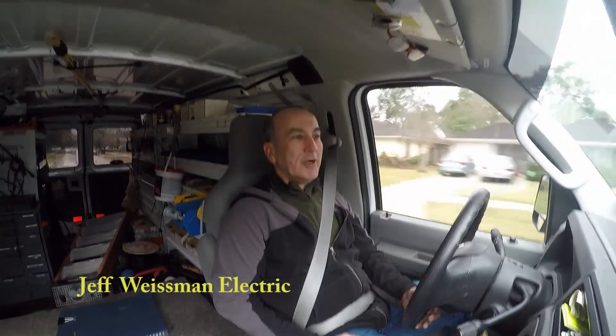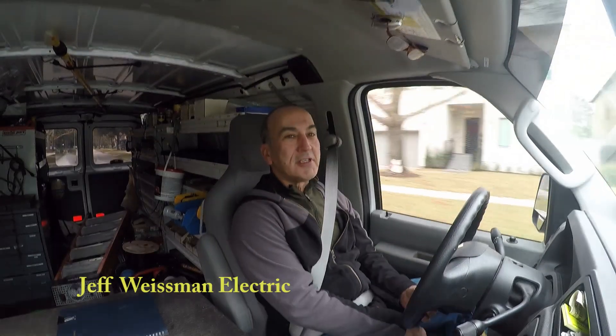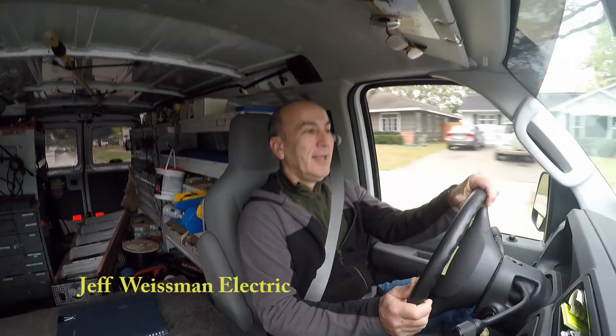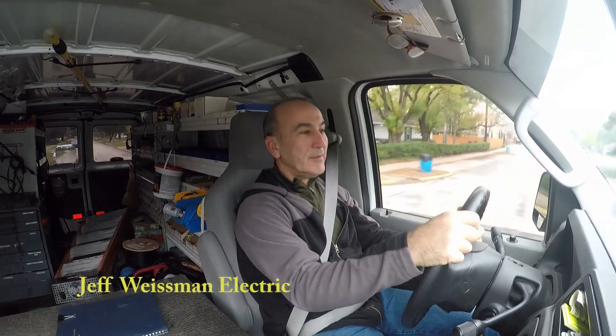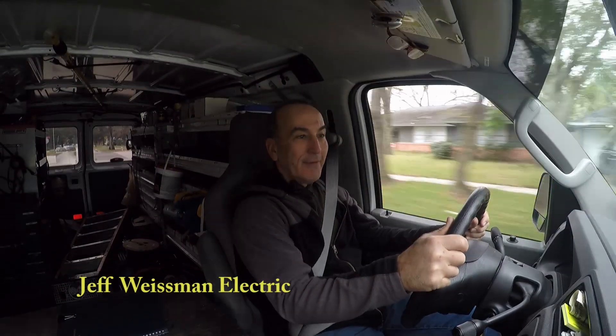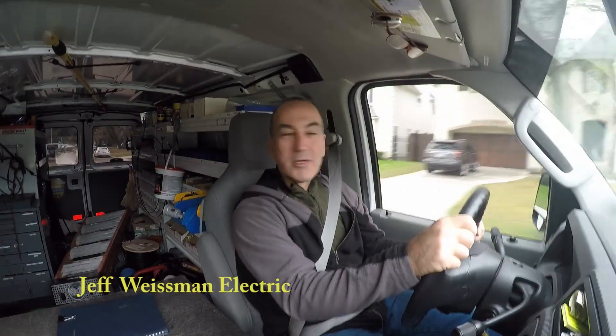So that's a way to get rid of the nuisance. The other way to get rid of the problem is to wait for those Christmas lights to dry out, or find where the nail or staple is in the wires — but that's not very practical. And if it rains again or your sprinkler system kicks on, it's going to happen again. I probably get about three calls a day for the last couple of weeks before Christmas with this same thing. So I hope that explains what's going on.